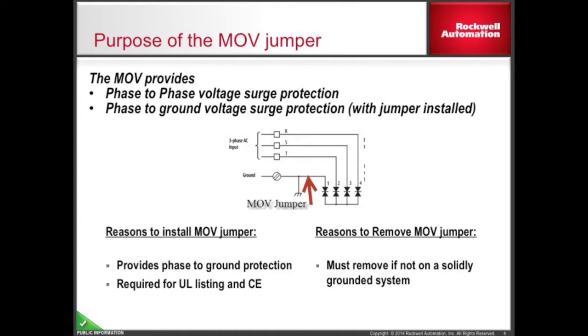The PE-A jumper should be installed on installations where the secondary of the transformer providing power to the drive is a Y connection with a solidly grounded neutral. This power system and jumper configuration is required on installations where UL or CE cabinet labeling is needed.